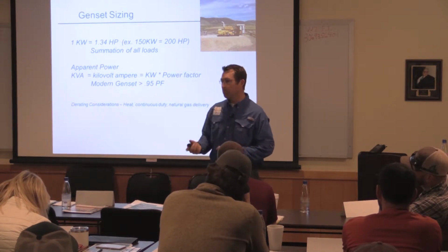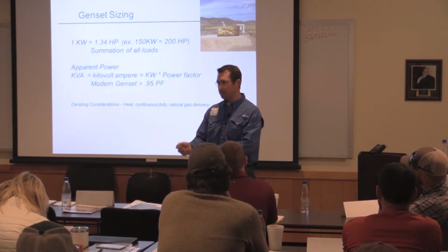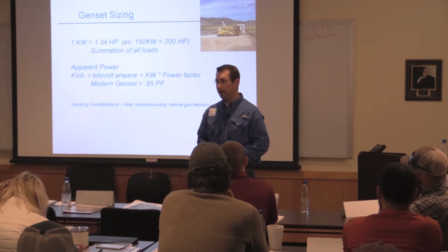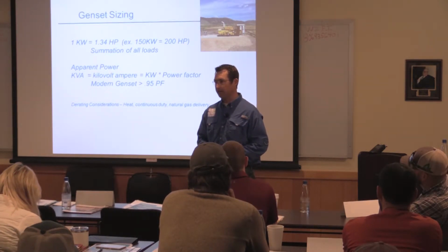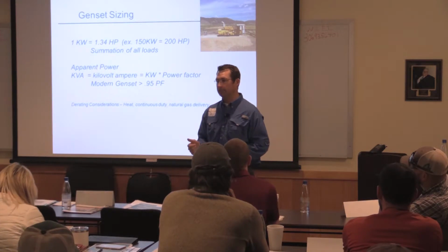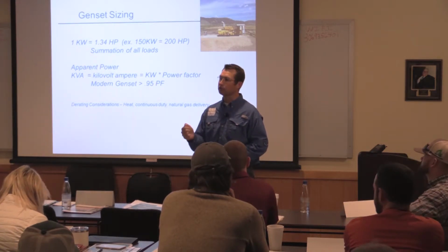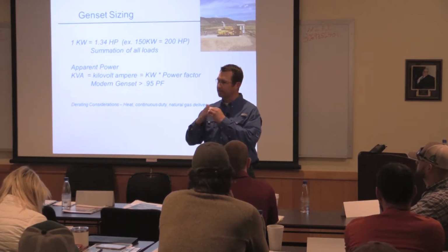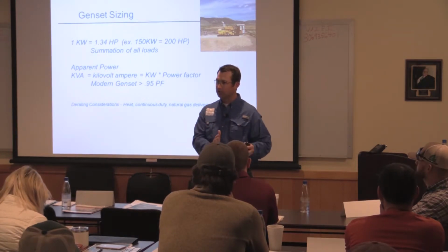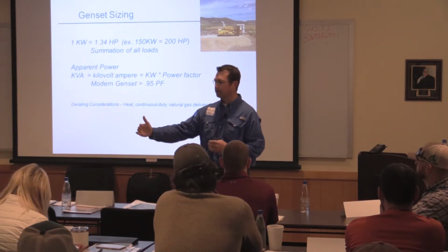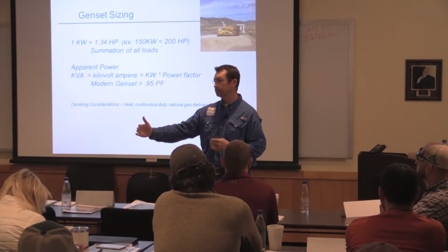So my range of what I actually measured on there ranged from as low as 75, so 0.75, which is, if you can imagine, you can't hardly close a contactor on that. You know, you'll see buzzing in the box at that point. But that's the lowest I have measured, all the way up to high 80s.